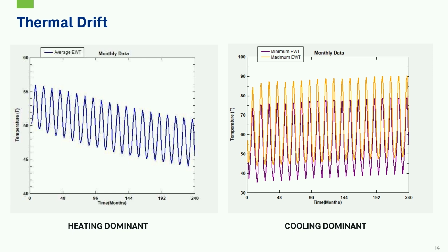Yeah, so the question is, why is our temperature range like 30 to 90 degrees, whereas in Europe we're seeing, I think, 25 to 100? 110, thank you. I think it's mostly because we are designing for the heat pump efficiencies that we're seeing in the equipment. And then I'm not sure if it's trying to go through the GLD iterations. It's mostly for those heat pumps and the efficiencies that we're seeing at really, really low temperatures or really, really high temperatures.